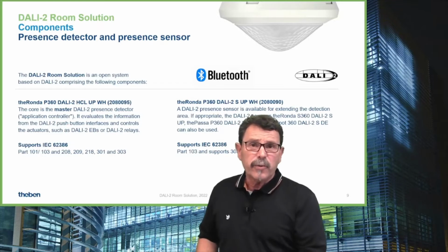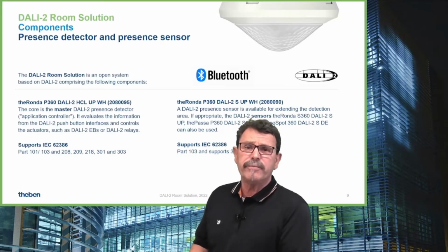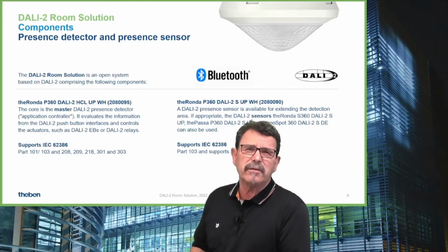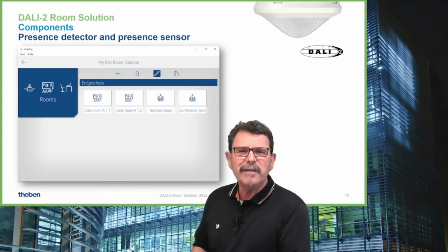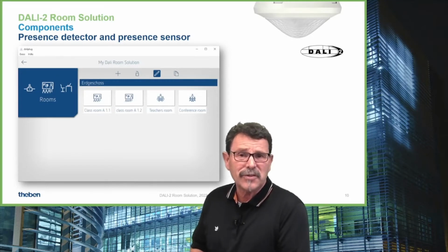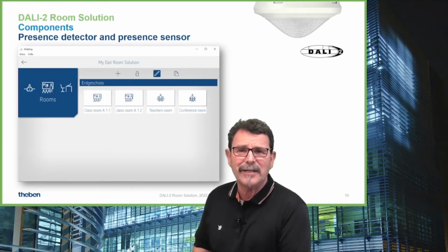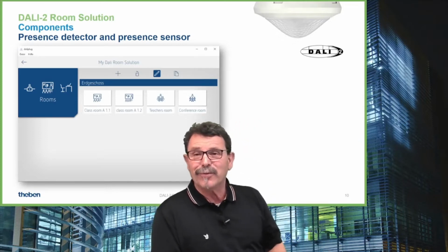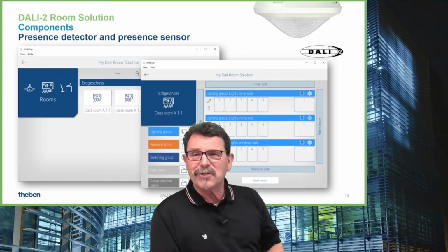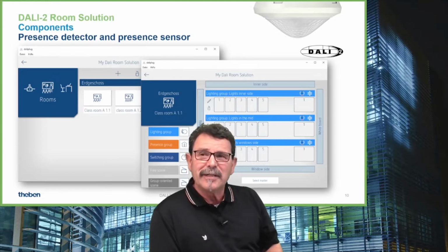This sensor gives you 24 meters of detecting area in the round, which is, as a summary, around 490 square meters, roughly, which is really powerful. And what you need furthermore is the software to do the configuration, to do the addressing of the respective light sources. And this software and the app, if you intend to do the assignment and configuration with the app, you find in the App Store, Play Store, however, and with this we can later on configure the respective lights. I will show you how it works.